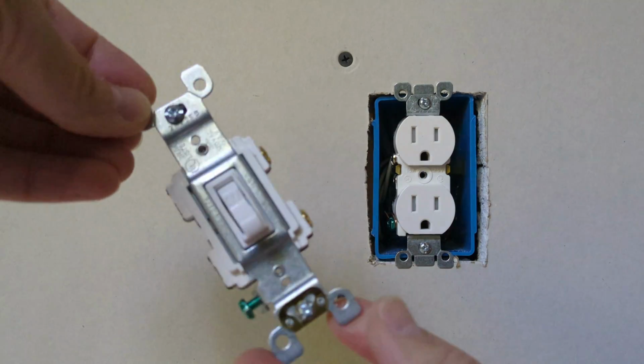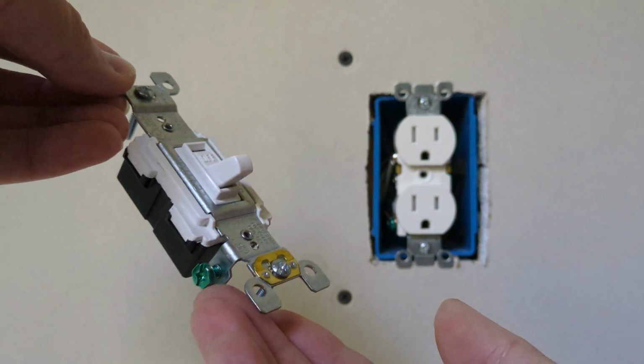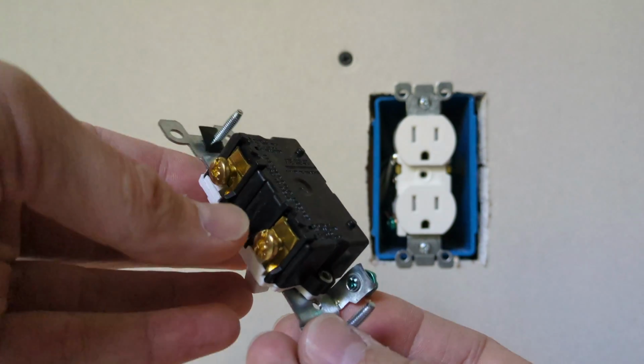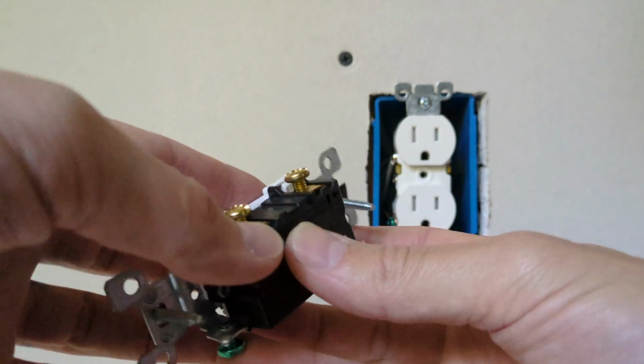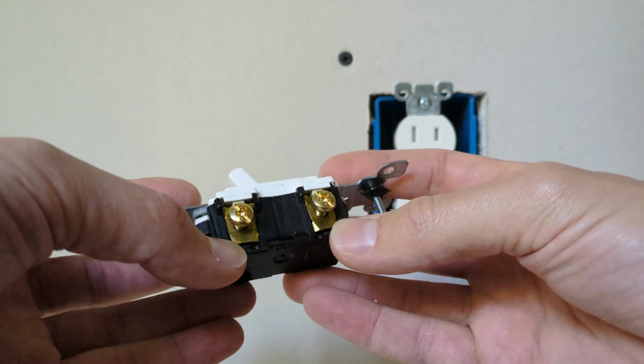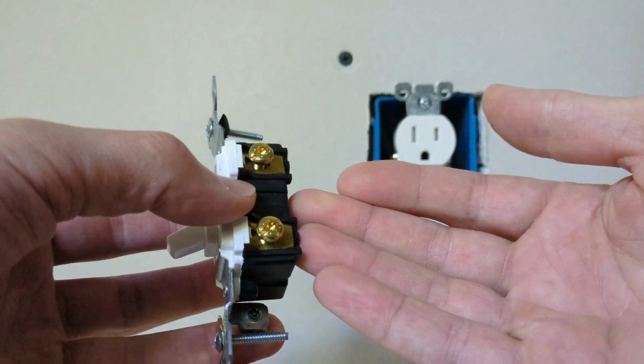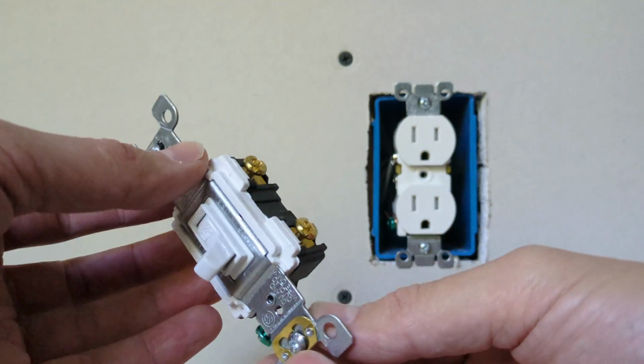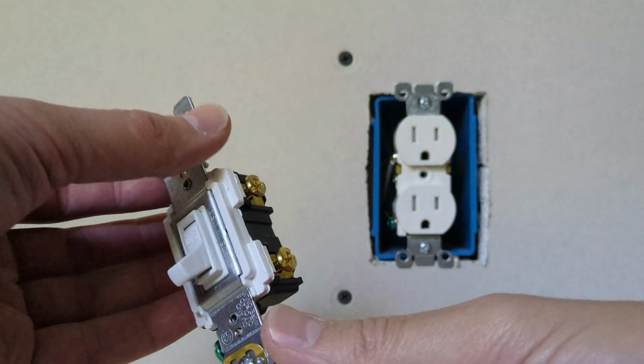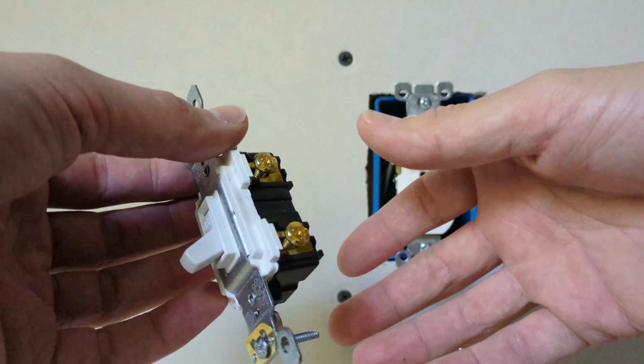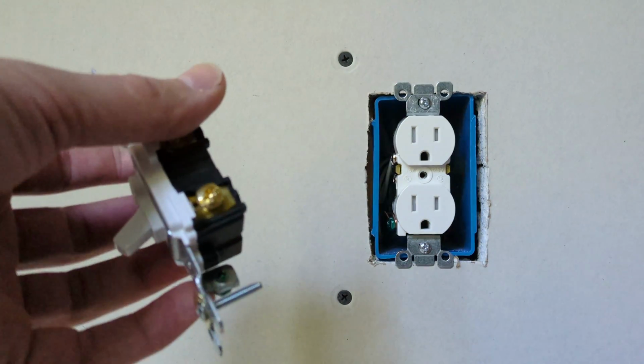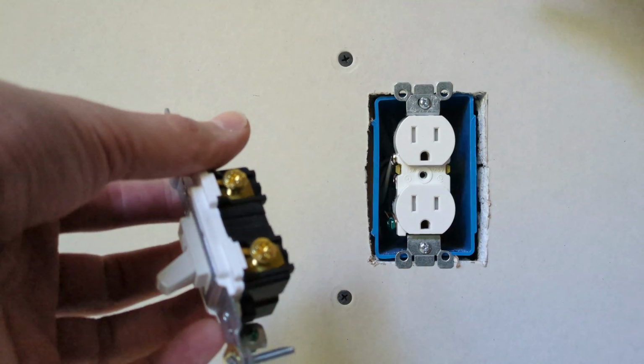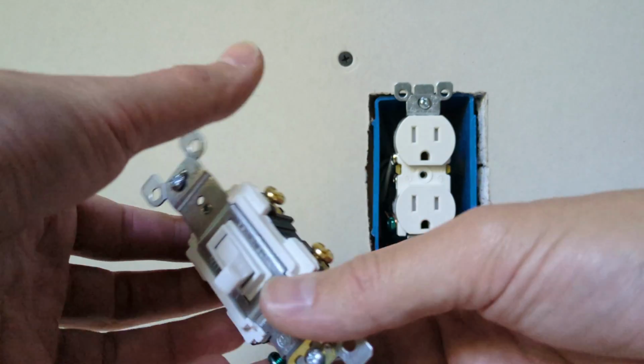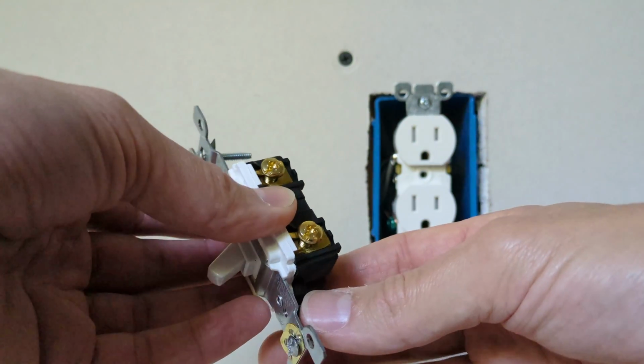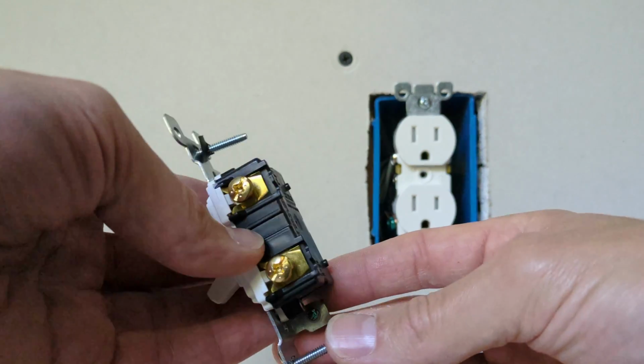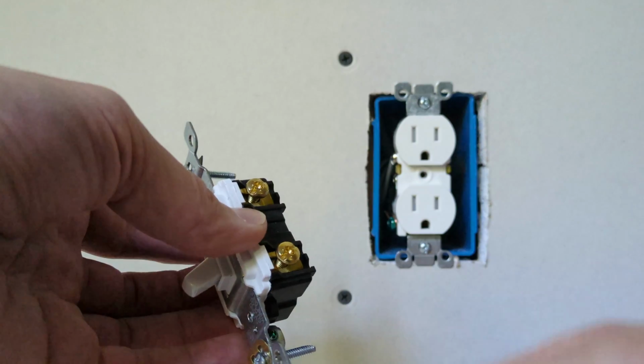For a light switch, most of the process is going to be about the same. You have a ground screw. You can see that it has the gold or brass colored screws because you're supposed to switch the hot black wire for a light switch. And I prefer to have all the wires coming into the switch box. So you have wires coming in for the power, you have wires from the light fixture coming into the box with the switch. So you connect your neutrals together in the box, and then you'll be switching the black hot wire.